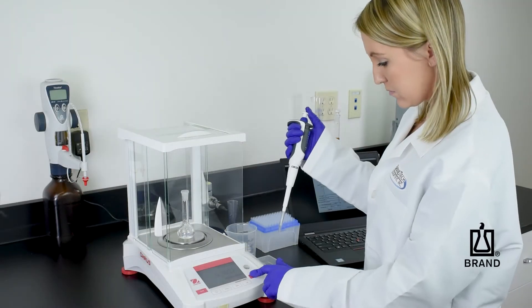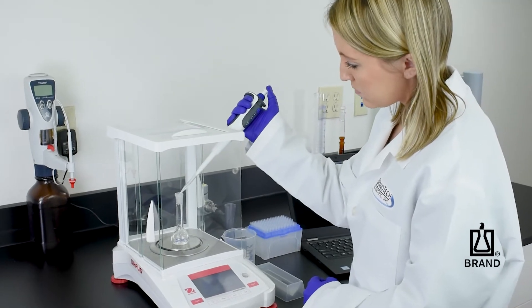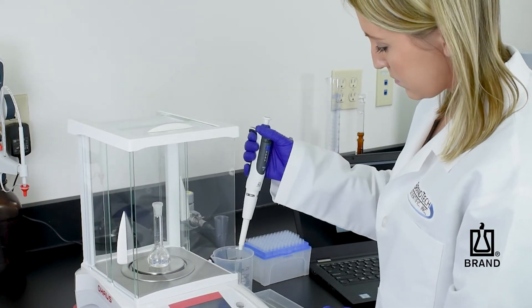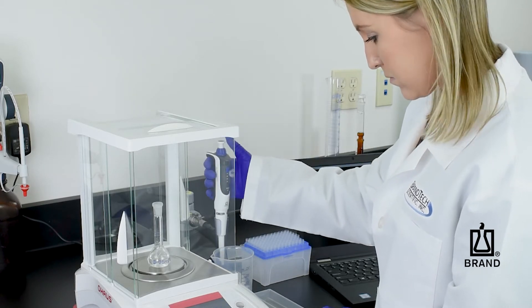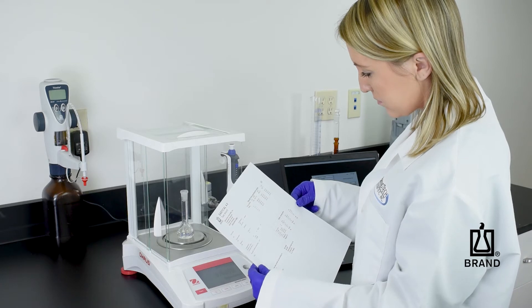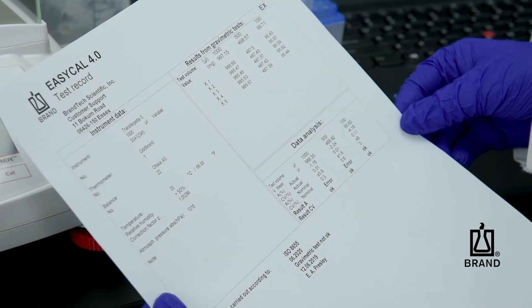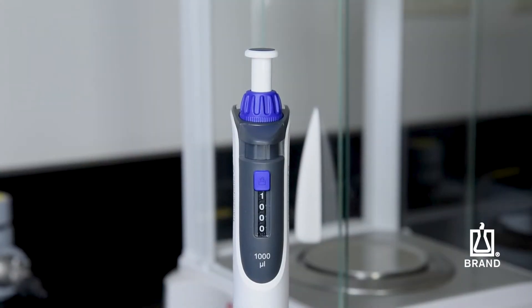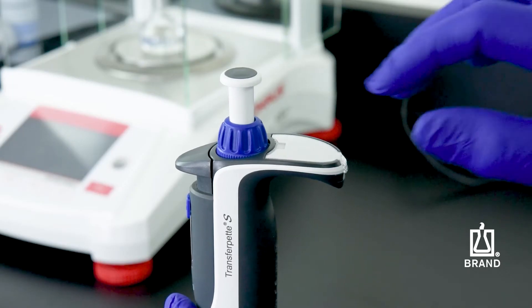First, gravimetrically determine the actual dispensed volume of the pipette. Our SOPs provide more detailed information. When the gravimetrically determined mean volume deviates from the volume setting beyond the permissible tolerances, it is necessary to adjust the pipette with the easy calibration feature. The Transferpette's display is easily adjusted to the gravimetrically determined volume.